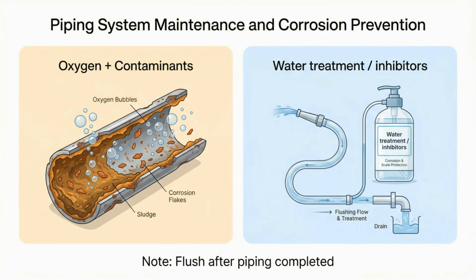After piping is complete, the system needs to be flushed to remove oils, grease, and debris. Then water quality has to be protected with appropriate chemicals because high oxygen content and contamination corrode steel components and can void warranty coverage related to oxygen contamination. Good water is not optional in hydronics.